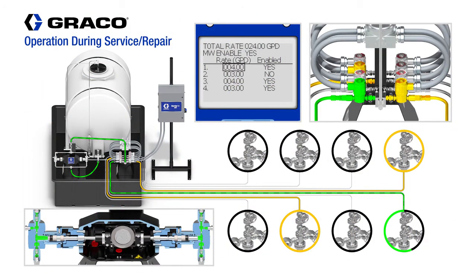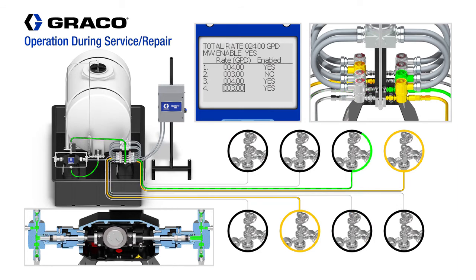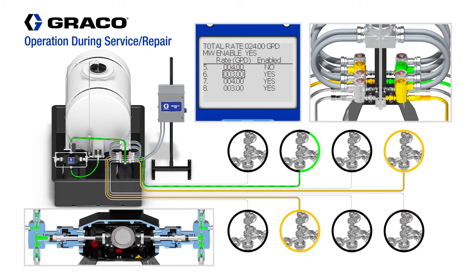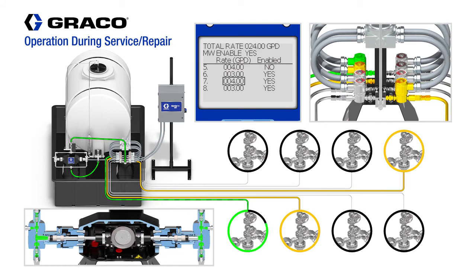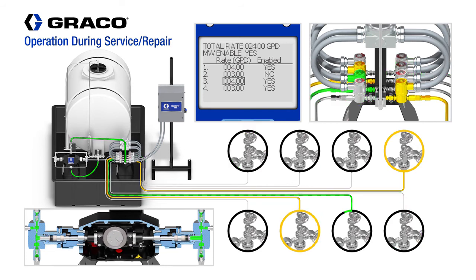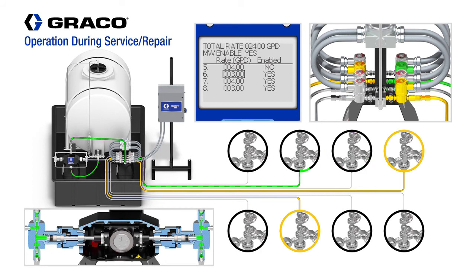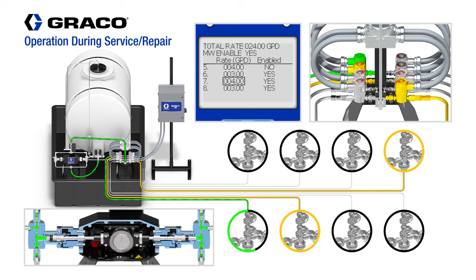Now let's take a look at what happens if we need to service or repair a solenoid valve. In this demonstration, we will show what happens when line 2 and line 5 are down for repair. When that happens, the Harrier Plus MPI controller will identify which lines are down and disable them. The dosing operation will continue to cycle while skipping the disabled solenoid valves. That way, you can replace the faulty solenoid valves without interrupting operation to the rest of the injection lines. Line pressure and individual line flow rates are maintained in the rest of the injection lines.